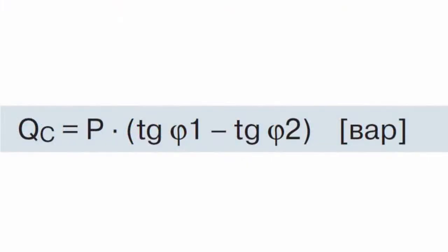The reverse magnetic energy returned to the supply grid can be temporarily stored in capacitors and then used for further alternation of the magnetic field. To select the right capacitor, the required reactive power Qc can be calculated using the following formula: Qc equals total power multiplied by the difference of tangents of angles phi1 and phi2.